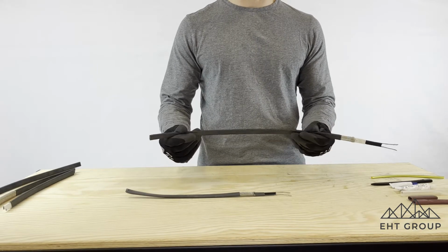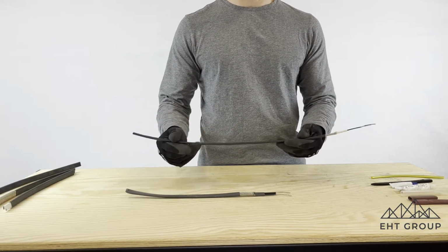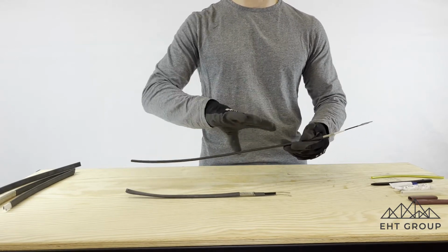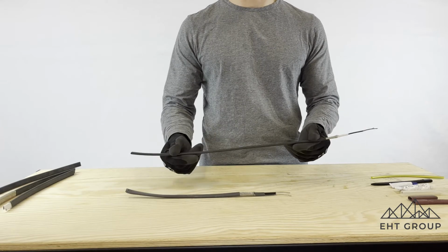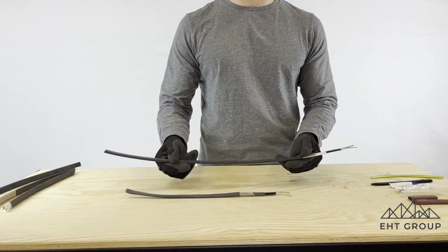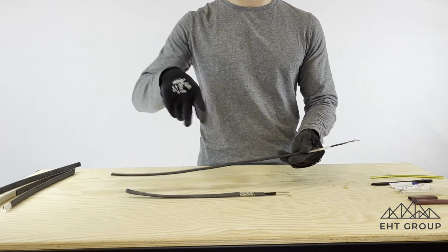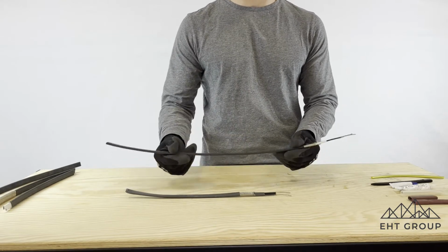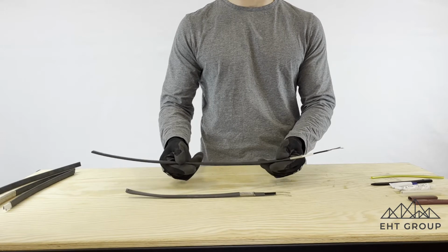The other beauty with it is that SR cable can touch itself. So when you're installing it, there's no concern if you're doing more than one pass, or if the cable is being installed on a heat sink and there's additional heat tracing that's routed, in that the heat trace cable can overlap and can touch itself without any overheating concern.